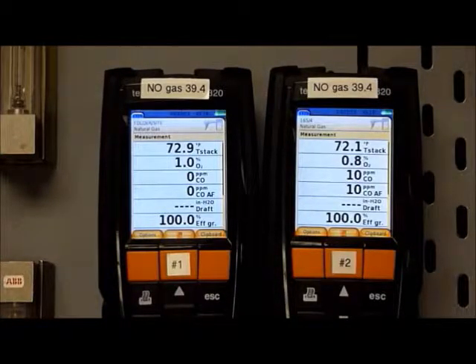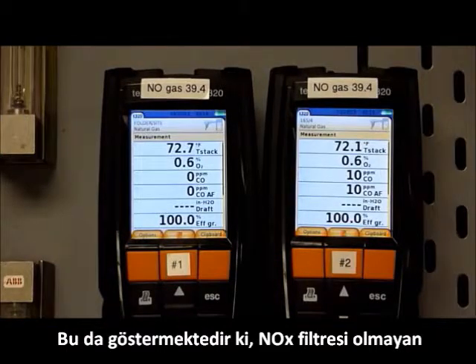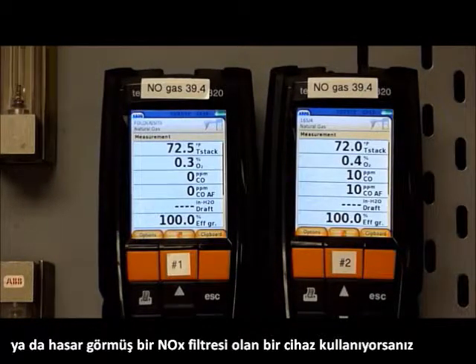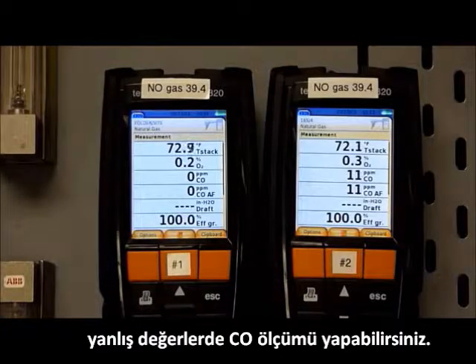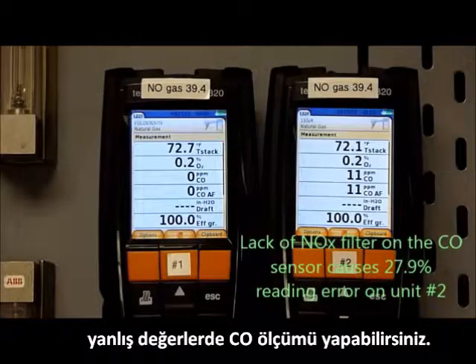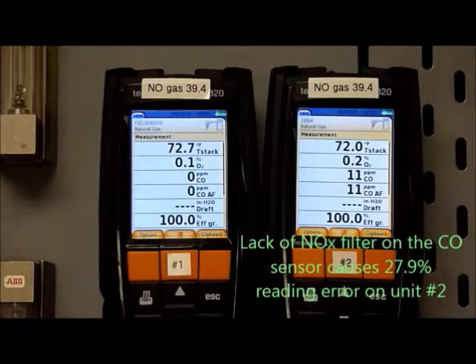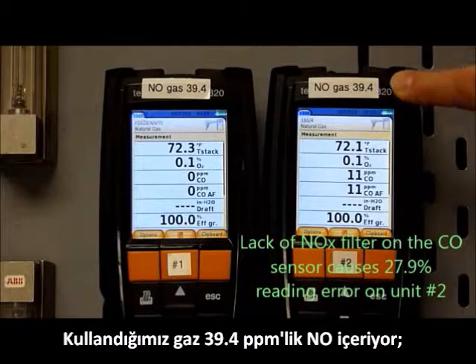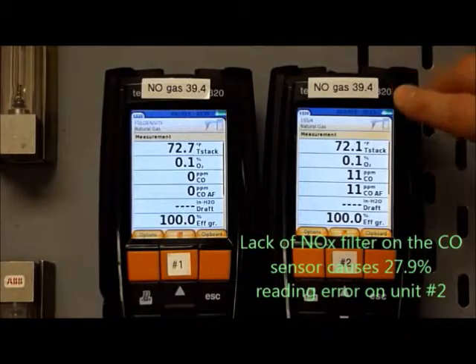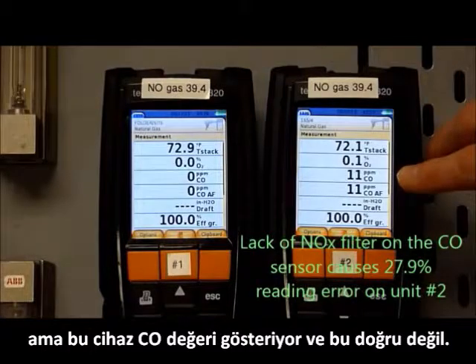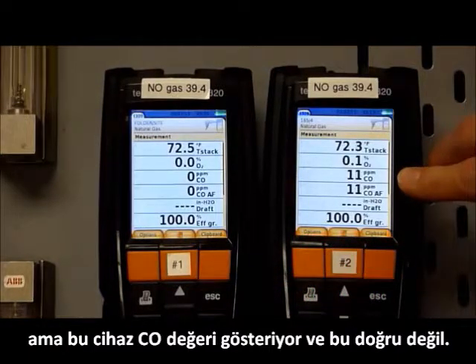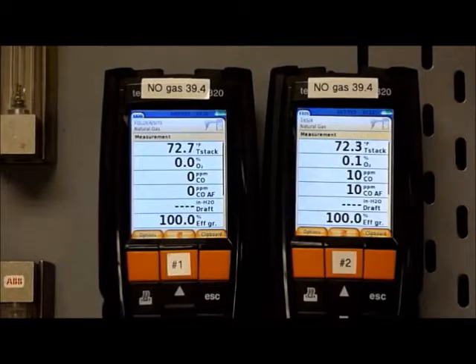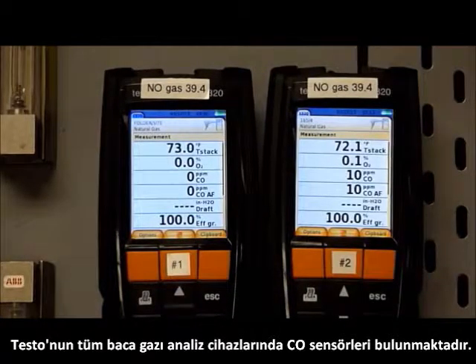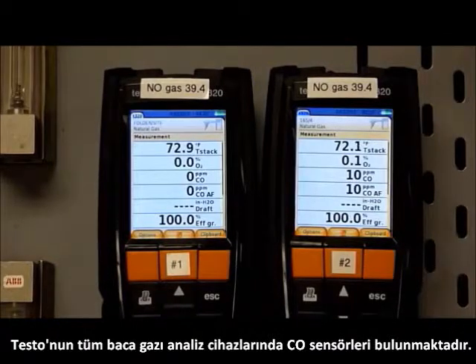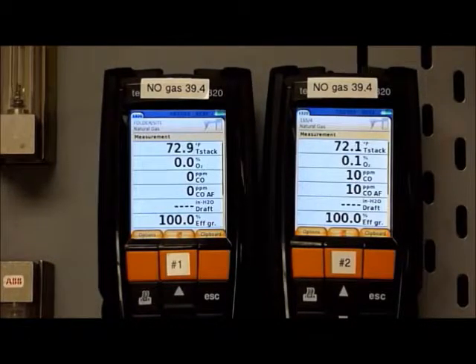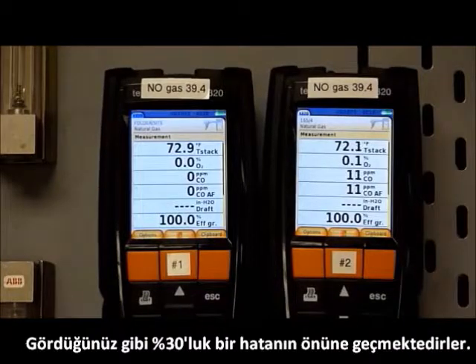What this demonstrates is that if you're using an analyzer that doesn't have a NOx filter or has a depleted NOx filter, you can be measuring CO at the wrong concentrations. So the gas that we're running is 39.4 nitric oxide, and this analyzer is showing a CO reading on nitric oxide, and that's what's not correct. All of our analyzers that Testo makes have CO sensors that utilize NOx filters. So as you can see, you could be almost up to 30% off.